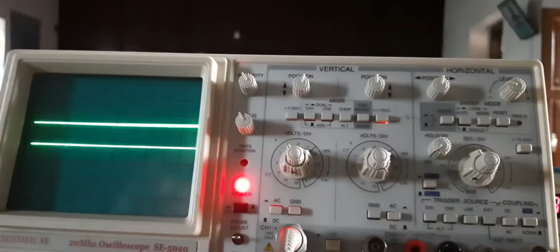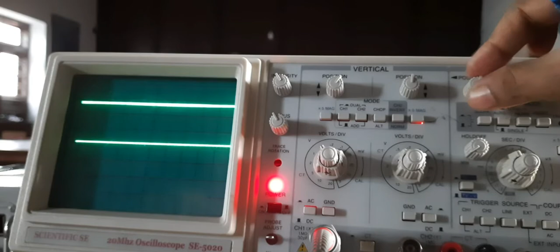Now I have pressed both channel 1 and 2. So you can see 2 channels. Vertical adjust for the first channel, vertical adjust for the second channel. Okay. Now comes the horizontal adjust. It is common for both the channels. I can move this trace horizontally with this horizontal adjust. It's a common knob for both the channels.